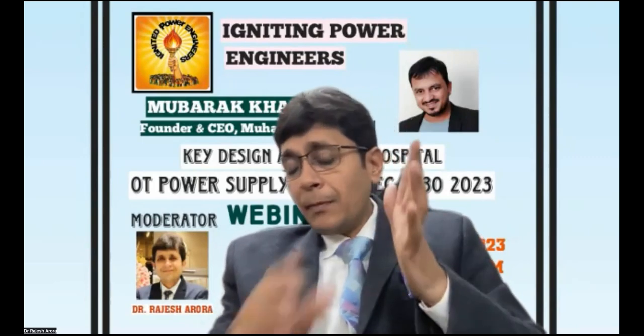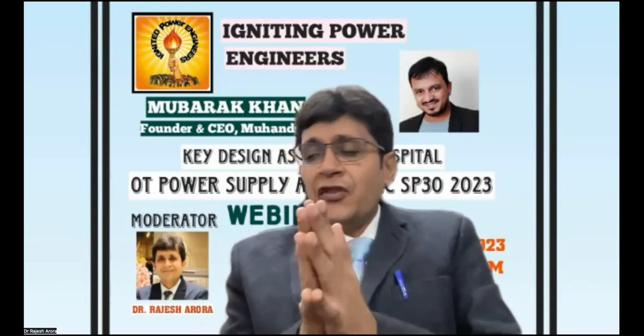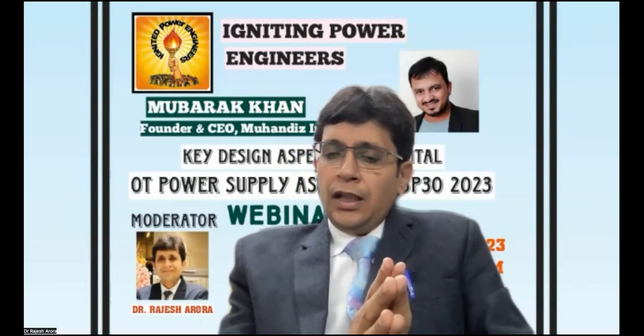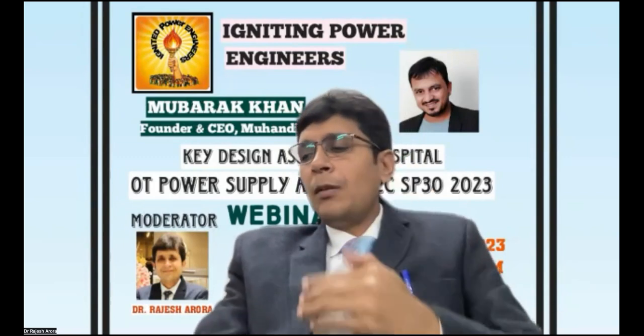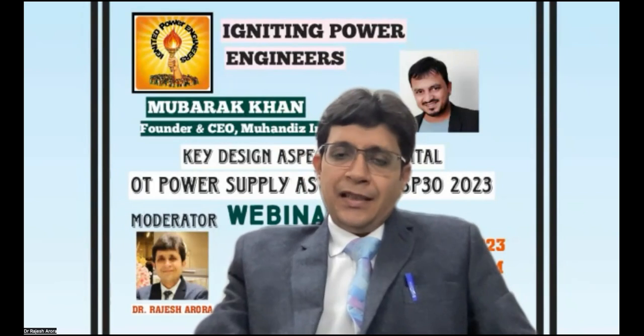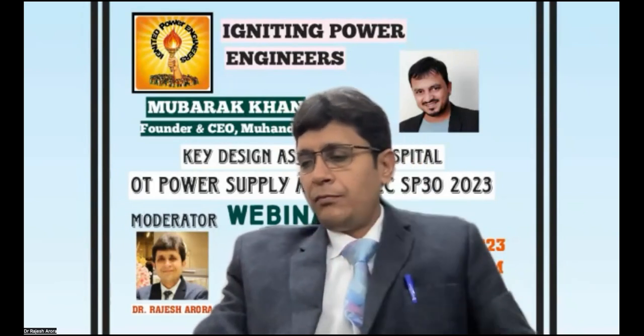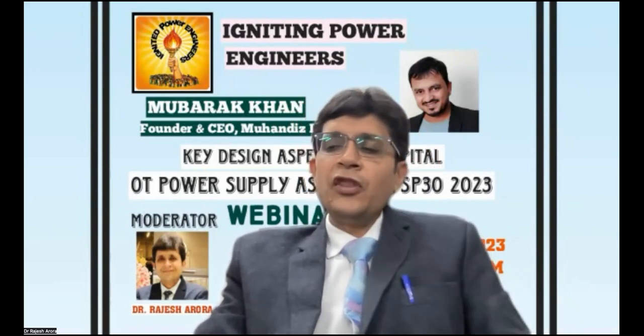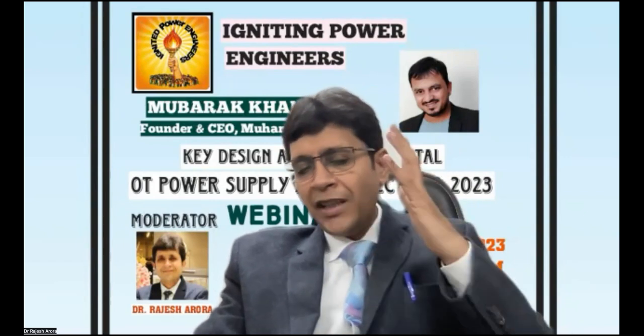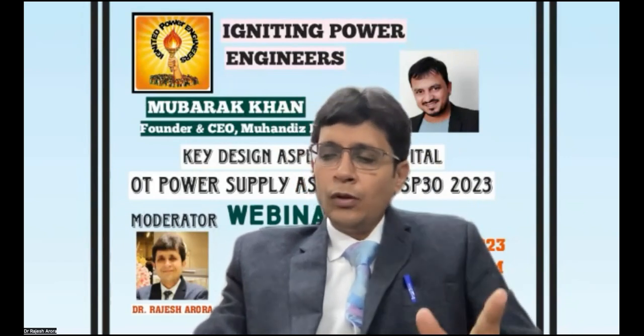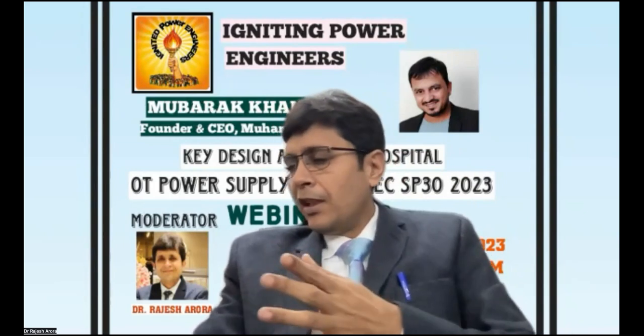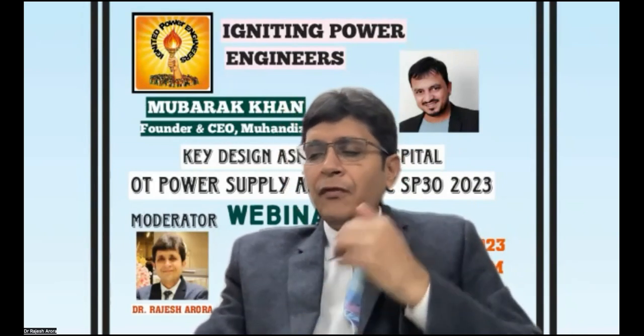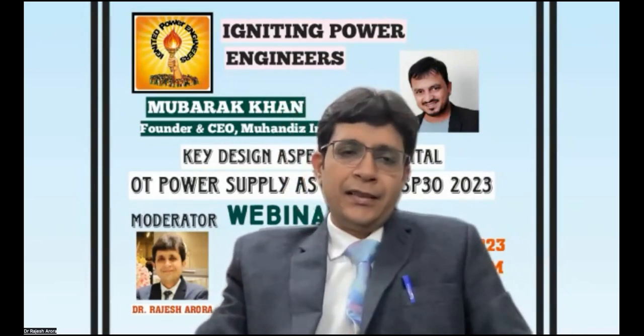We should not forget about the initial and the periodic inspection and verification. An important part is the changeover period and the EMI, electromagnetic interference. We have to understand the classification based on the safety services for medical locations like Class 0, Class 0.15, Class 0.5, Class 15, and Class more than 15 seconds.